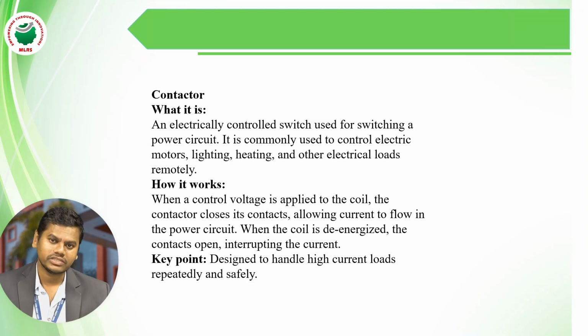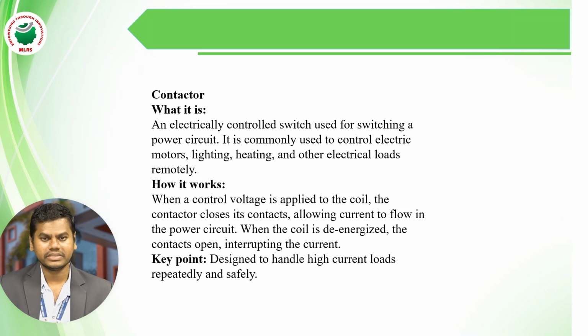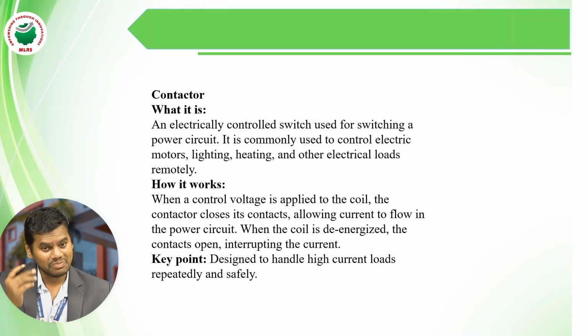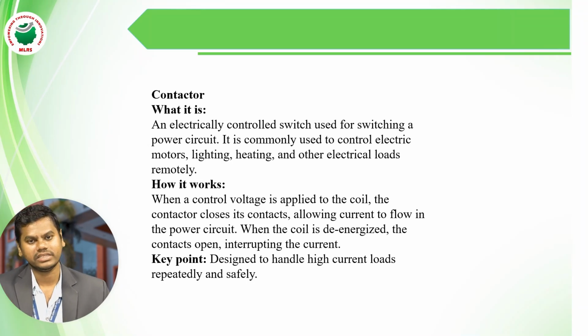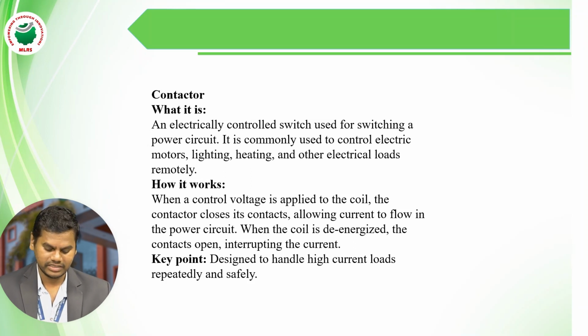But how does it work? When a control voltage is applied to the coil or solenoid, the contactor closes its contacts, allowing current to flow in the power circuit. When the coil is de-energized, the contacts open, interrupting the current. The key point is that it is designed to handle high current loads repeatedly and safely.